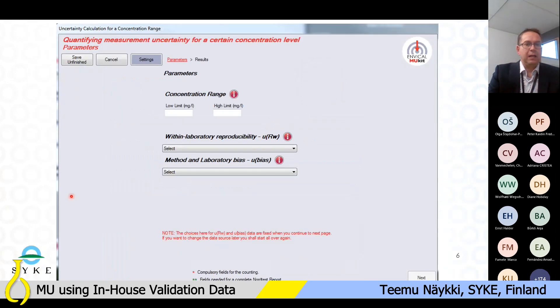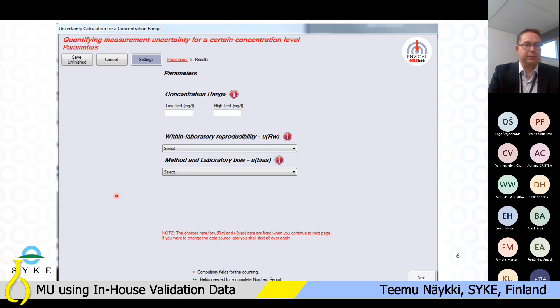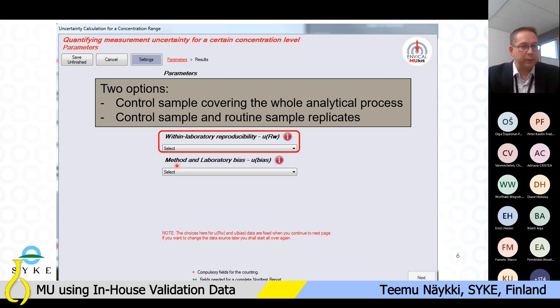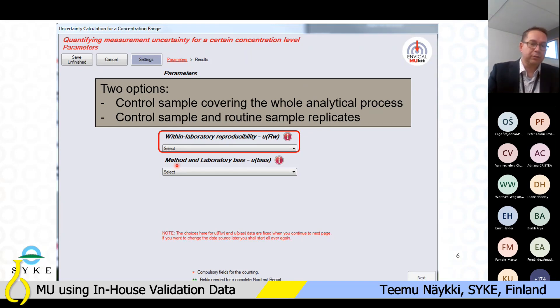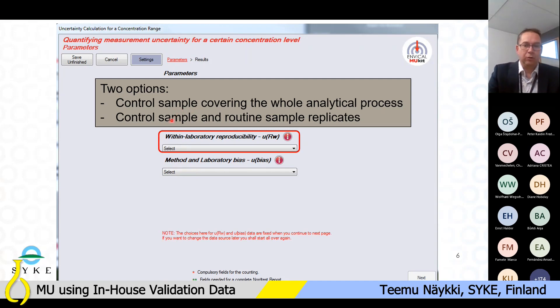When you start your evaluation process, you need to choose the way you are calculating the precision component — that is, within-laboratory reproducibility. For within-lab reproducibility, there are two options: you use results from a control sample that covers the whole analytical process, or you use results from both a control sample and routine sample replicates.